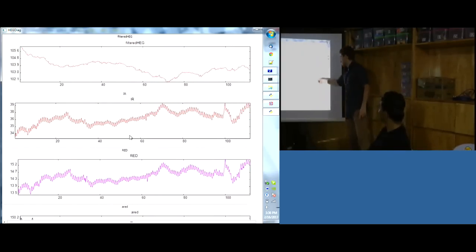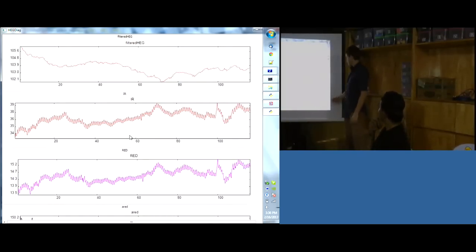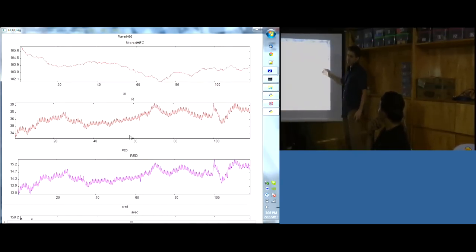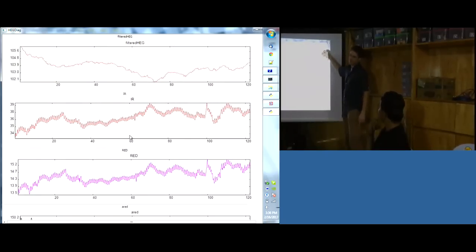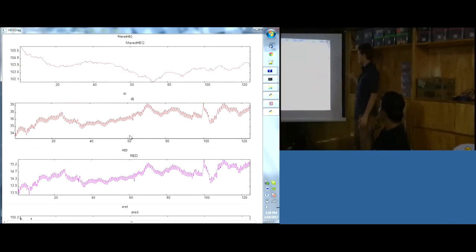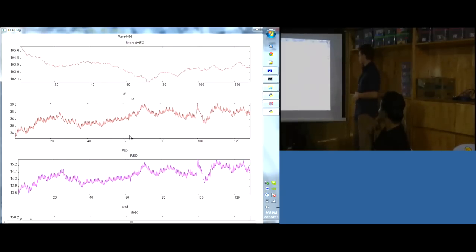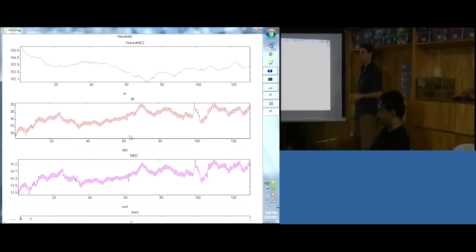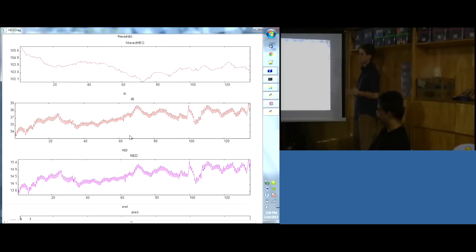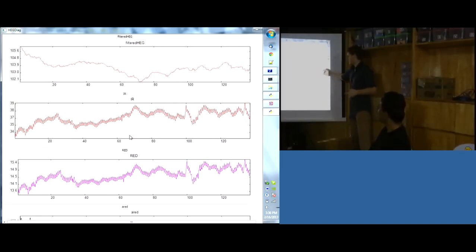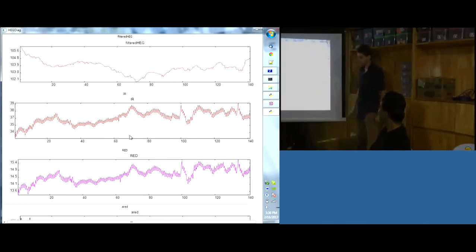These large spikes and these Mayer waves show up very well in the raw absorbance or transmittance data, but they don't show up very well in the ratio data, the oxygenation data. And that's the main point of taking that ratio. Total blood volume is really interesting and a great thing to measure if you can, but it's hard to measure because there are a lot of noise sources that influence it. Most of the noise sources that influence each of these raw readings influence them equally, and so don't influence the ratio very much.